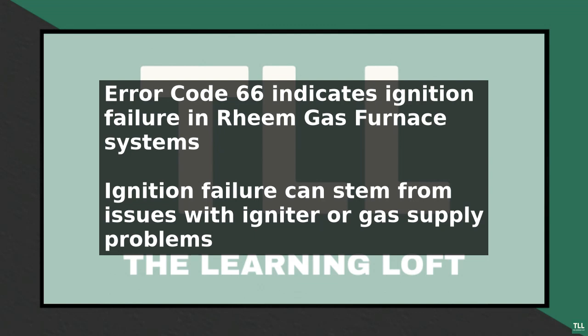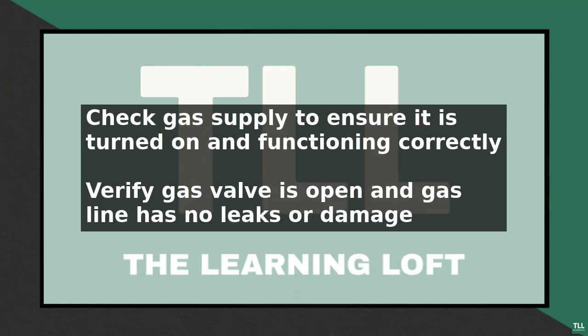This issue can stem from several potential causes, including problems with the igniter, gas supply, or the furnace's control board. To troubleshoot error code 66, start by checking the gas supply to ensure it is turned on and functioning correctly. Verify that the gas valve is open and that there are no leaks in the gas line. Next, inspect the igniter for any signs of wear or damage. If the igniter is faulty, it may need to be replaced. Ensure the igniter is clean and free of debris, as a dirty igniter can also prevent proper ignition.